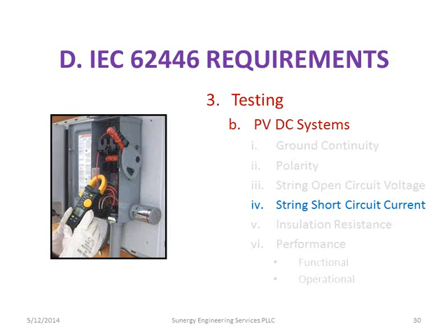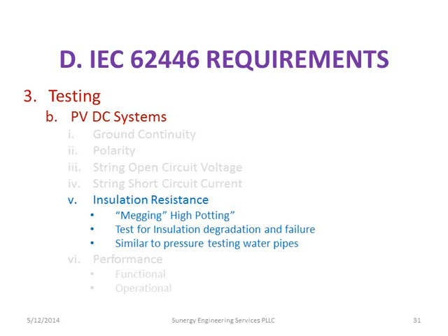And then insulation resistance, which some people call megging. I think in the inverter world they call it high potting. Basically you put a high voltage through the system, and if there's some place where there's a small nick or where it's rubbed up against metal somewhere, it'll flash over and you'll get conduction through that piece, and then you'll have a very low resistance measurement when that happens. So you're looking for a very high resistance measurement, showing that all the insulation is in good shape going down through the wiring. It's kind of similar to pressure testing pipes.